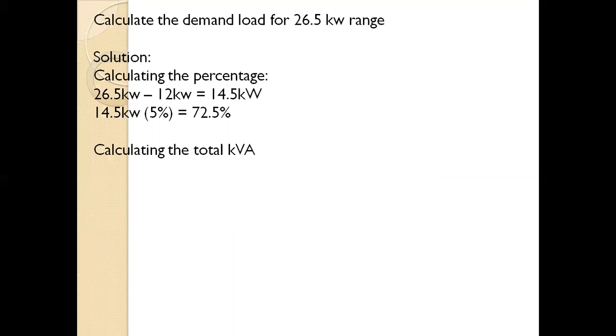We also have a sample: calculate the demand load for a 26.5 kilowatt range. As you can see, there is only one kitchen equipment, but more than 12 kilowatt capacity. So what is the solution? 26.5 minus 12 kilowatt is 14.5. Then 5% of 14.5 is 72.5, so 72.5 plus 100% is 172.5%. Then 172.5% times the first demand load of 8 gives a total of 13.8 kVA. That is the total demand of our 26.5 kilowatt capacity range.